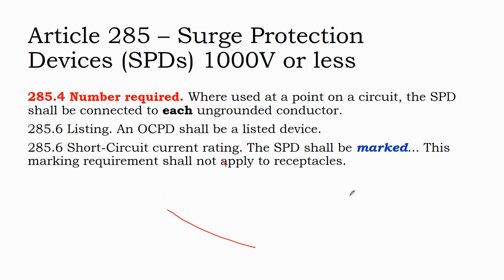Surge protection devices. It's common to put lightning arresters on your equipment. It says where used, they can be connected to each ungrounded conductor. And so you'll get lightning arresters that are listed for particular services. What that might mean is that if you're using a 240 volt split phase surge arrestor, you're connecting to each leg of power. Now you want to use a lightning arrestor that is marked or actually designed for your particular electric service. They cost about $20 or $30 each.